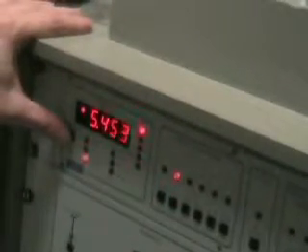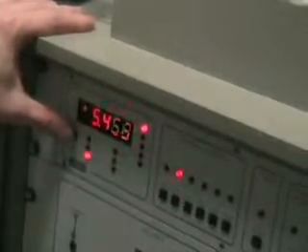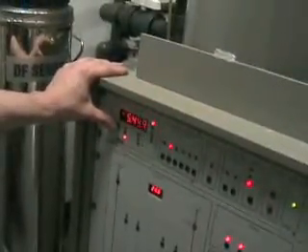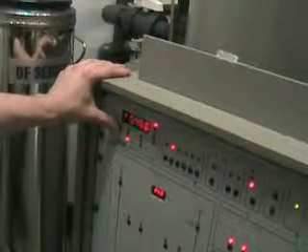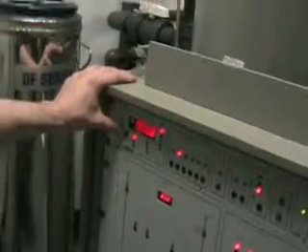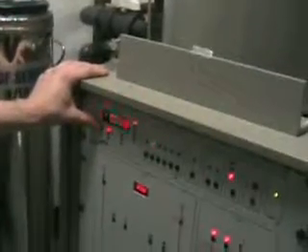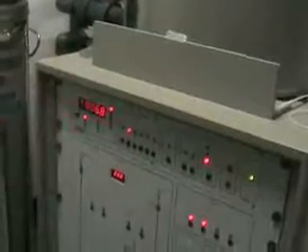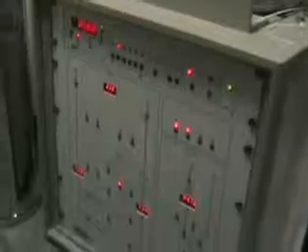It's cooled down. The sorb temperature is at 6 or 7 Kelvin. The mixing chamber is at 5.4 Kelvin, and the 1K pot is at 5.4 Kelvin. I put a little bit of helium into the 1K pot at one point just to let it trickle in — not pumping on it — to lower the temperature a little bit. I'll just sort of let it sit there. We could probably draw a little more helium into the 1K pot. Things are cooled down.